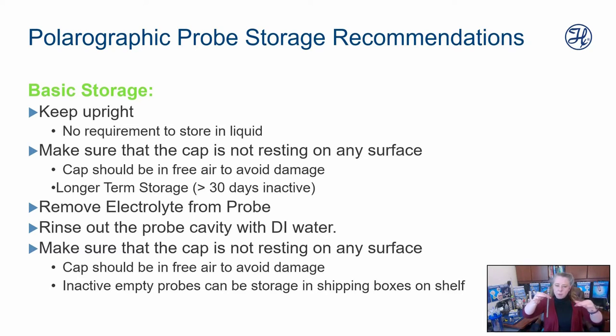When you store them, you do not want to leave them resting on a surface. You want to always make sure that that membrane cap is surrounded by air so it does not get micro cracks or damage the cap. Okay. And if you're going to store it long term, not only should you remove all the electrolyte, but you should rinse the cap out, just like you saw me do there, so that it's clean.